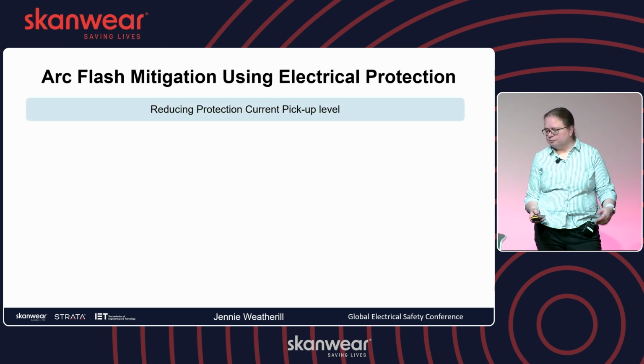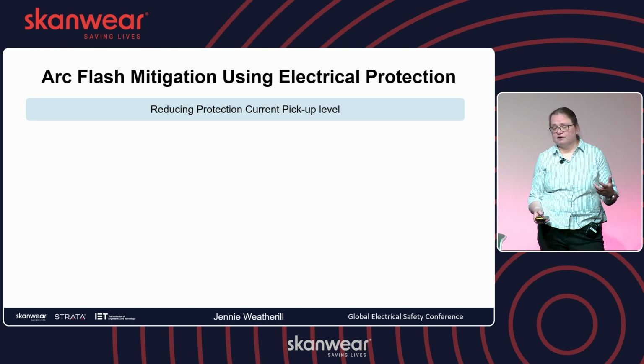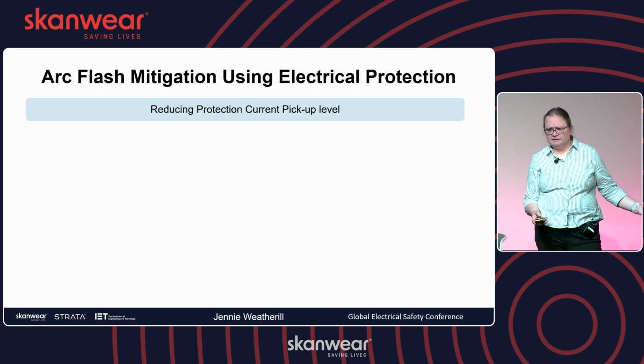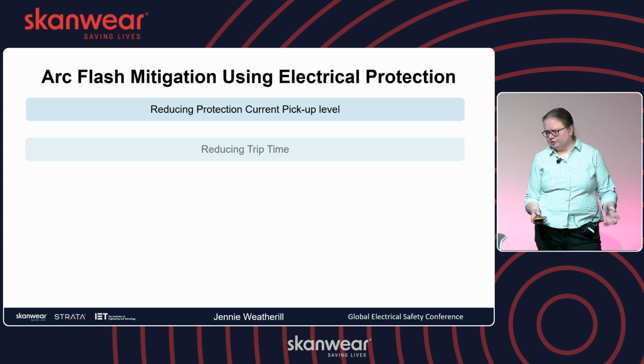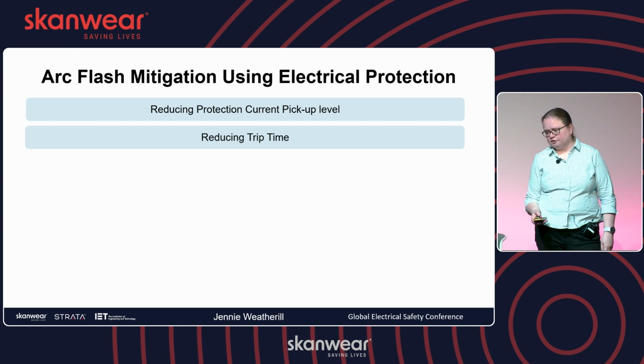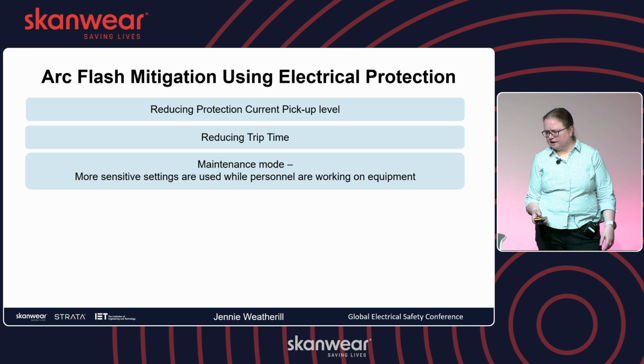So we can reduce the current pickup level. This can, though, cause problems with discrimination. If you make it too sensitive higher up, then you lose more of the system. So it's something to be thought about. Again, with reducing trip time, are you going to interfere with levels further down?